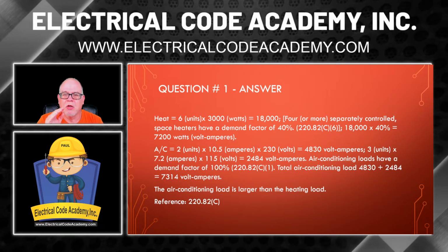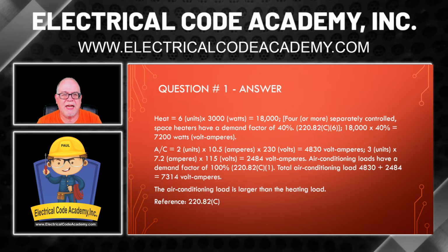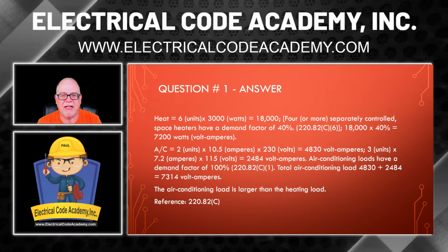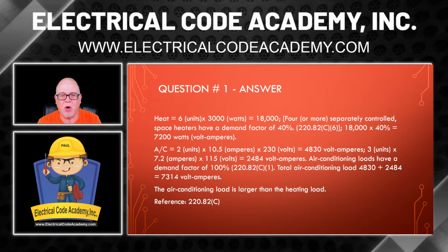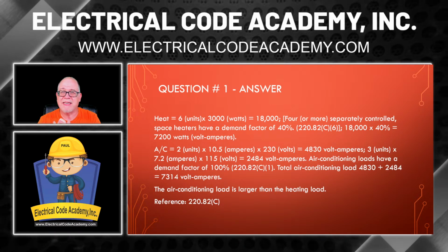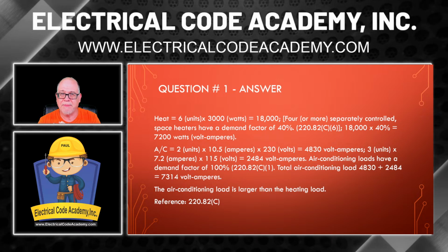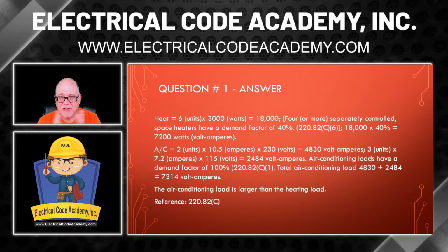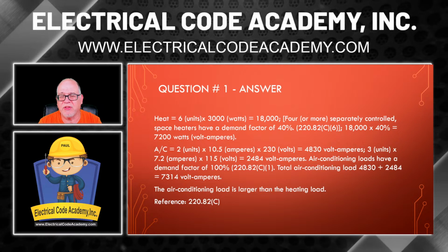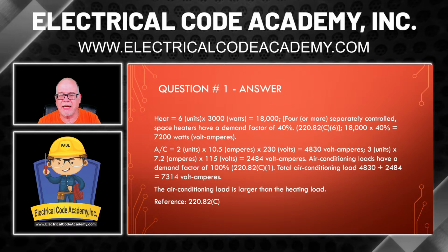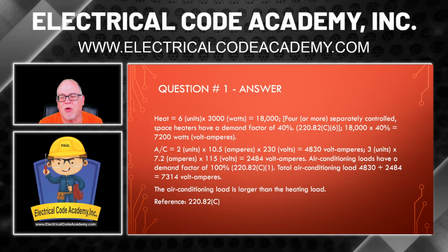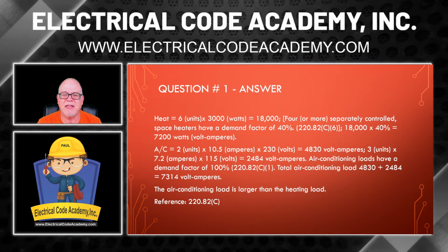All right. So now we want to do 3 times 7.2 times 115. That's 2,484 VA. So all we're going to do, remember, we take them at 100%, right? So we're going to add the 2 together. So 4,830 plus the 2,484, add them together. That's 7,314 VA.